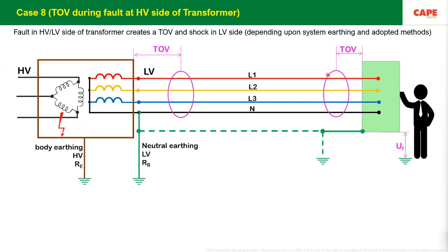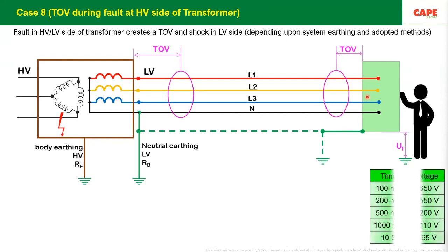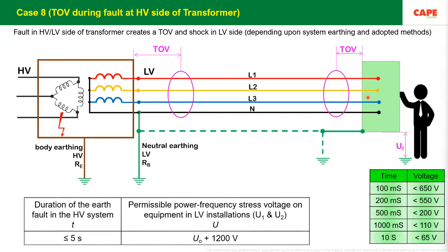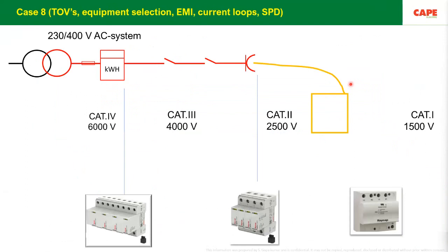Temporary over voltages up to 5 seconds can come into your building, which can create a shock hazard, which can create a failure of apparatus. And technically speaking, the shock voltage and the fault voltage must be limited to lesser than a certain limit. But unfortunately, this is also a subject which is new for most electrical engineers. Surge protective device, case number 8, protection against transient over voltages.